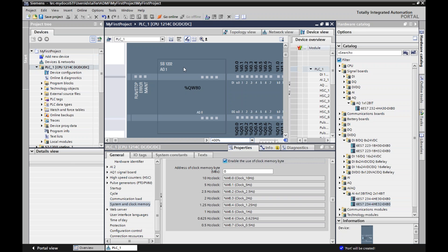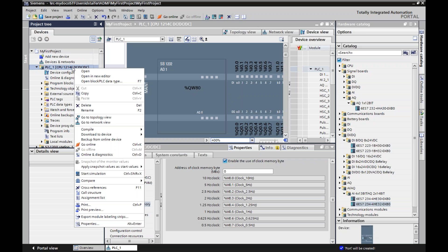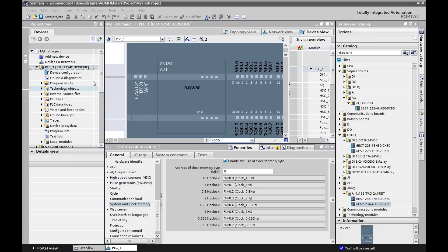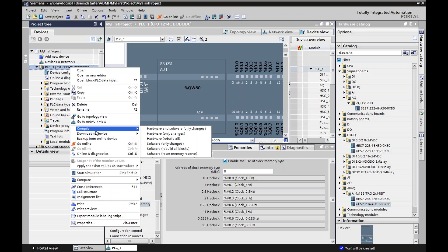So once I have all this hardware, I want to point out that some programming languages will automatically compile before they download, but others will not. Mitsubishi for one — you need to compile first and then download. Siemens is like that too, where I have to compile first before I download. There are a couple of ways of compiling. I can right click on the PLC itself to open a menu and you can see right here where it says Compile: Hardware Changes, Software Changes, Rebuild All. Anytime you make a change in the hardware on this screen, you should apply your changes, compile, and download.